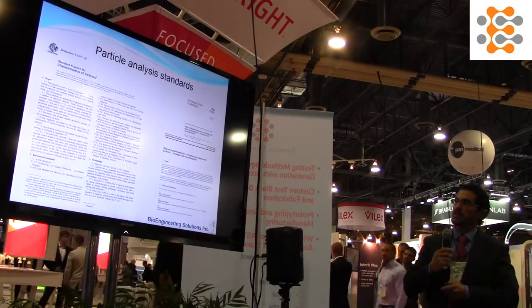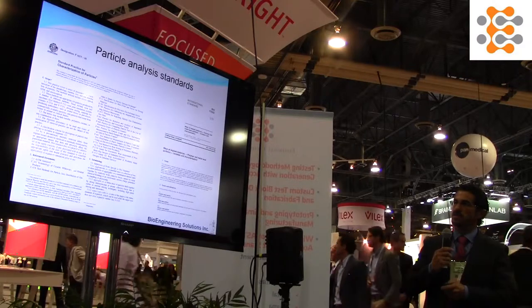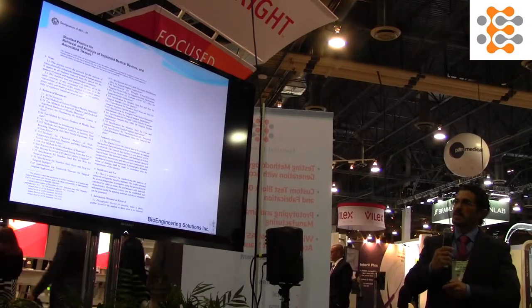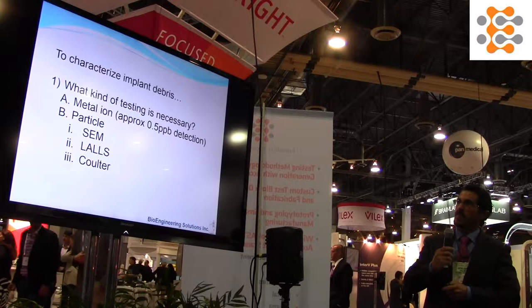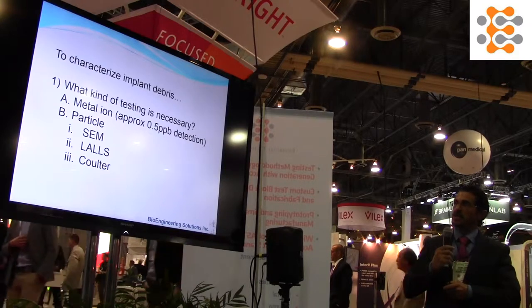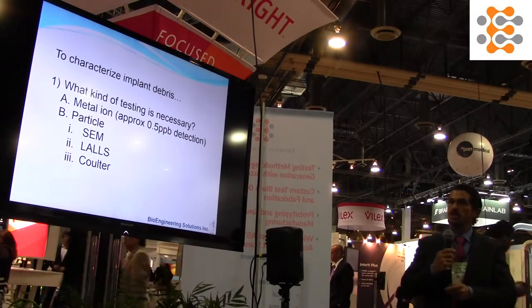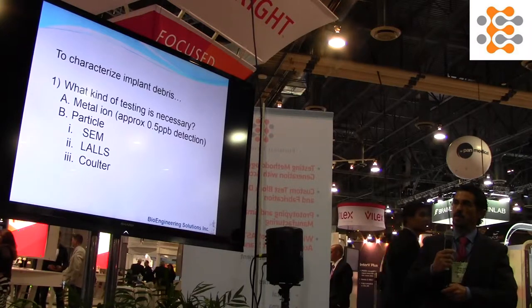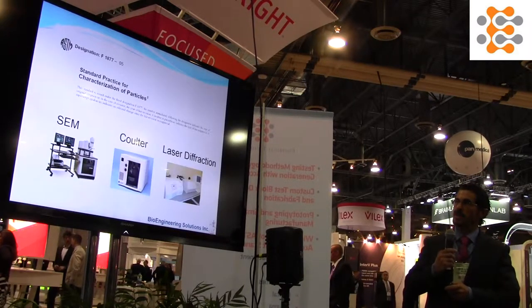These are the standards — ASTM 1877 — that we follow for particle size analysis. What kind of testing is necessary? Generally of your simulator fluids, it's a metal ion and a particle analysis, and there are a couple of techniques to use for particle analysis.